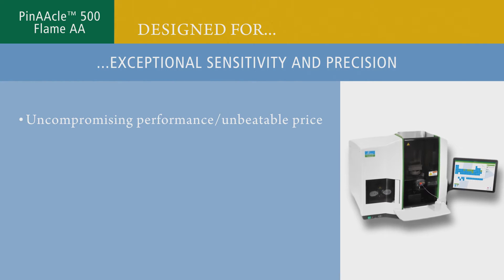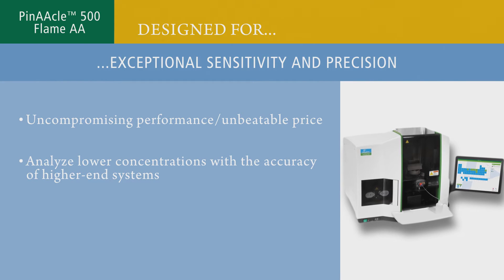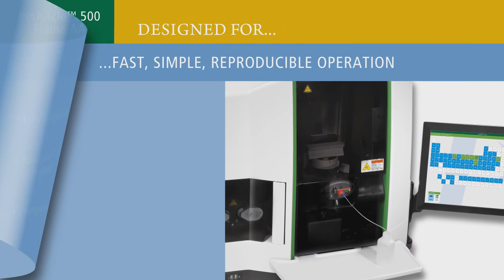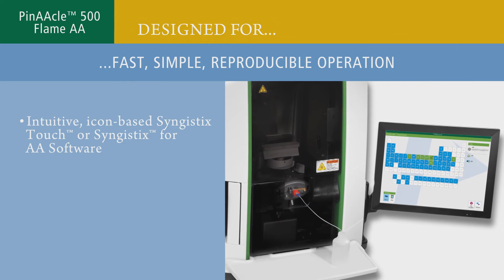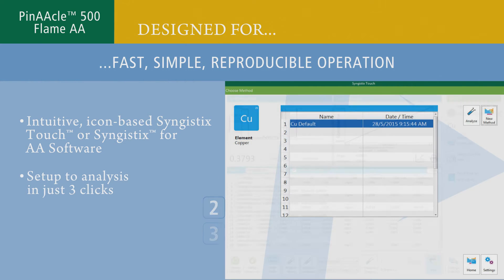Sensitive and precise, the system delivers an uncompromising level of performance at an unbeatable price, allowing you to analyze lower concentrations with the accuracy of higher-end AA systems and consistently achieve precision of less than 0.3%. PinAAcle 500 can be run using intuitive icon-based Syngistix Touch or Syngistix for AA software that lets you go from setup to analysis in just three clicks.